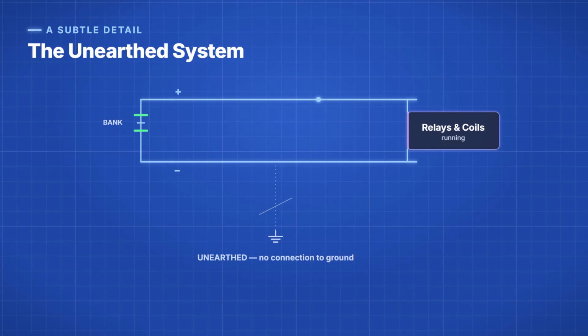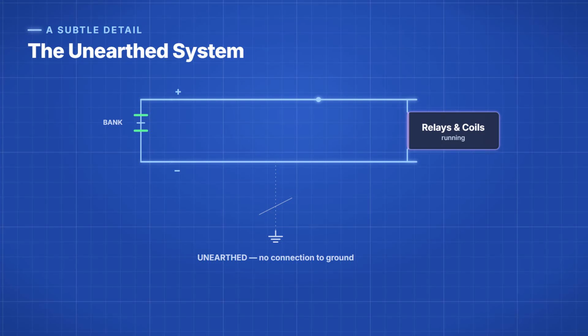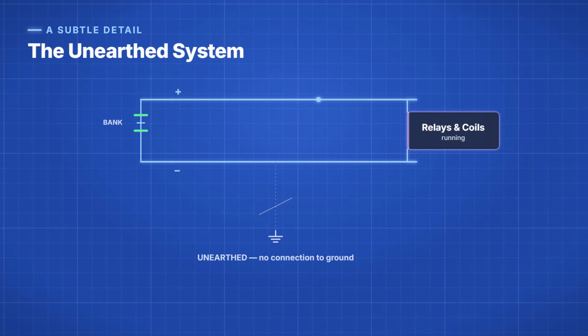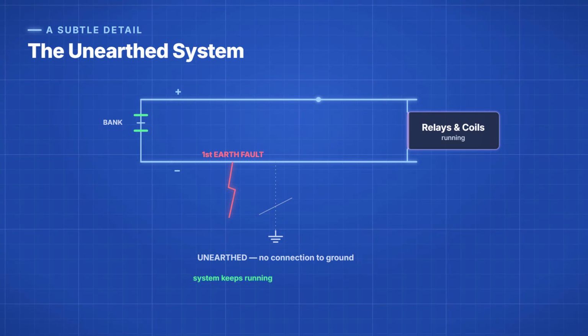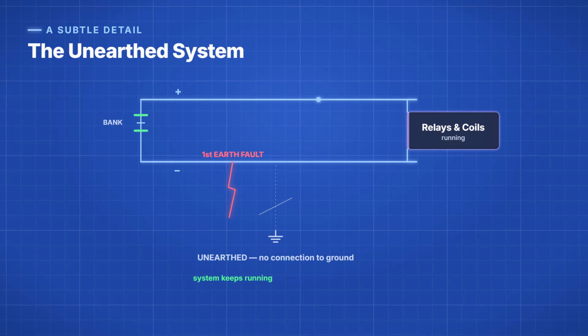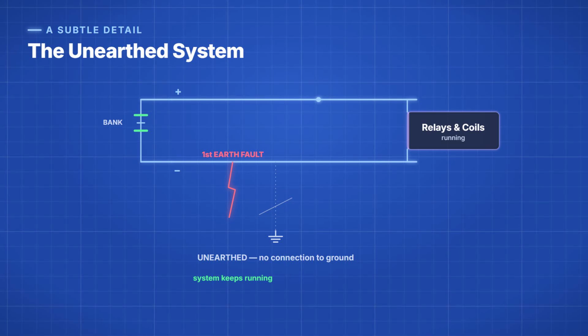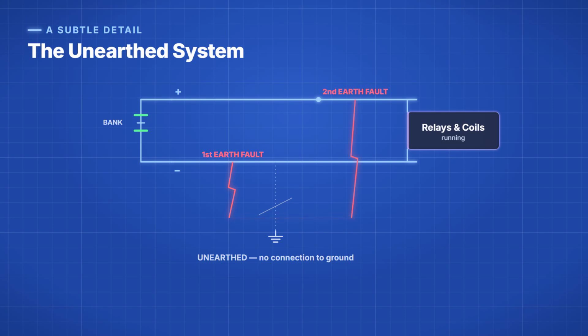That means neither side of the battery, the positive or the negative, is connected to ground. Here's why that helps. If one side accidentally touches ground, you get a single earth fault, but nothing actually stops working. The system keeps running, and your protection stays fully available. Even so, that first fault needs to be found and fixed quickly. Because if a second earth fault then appears on the other side, the two faults together form a path that can short the battery or even trip a breaker on its own.